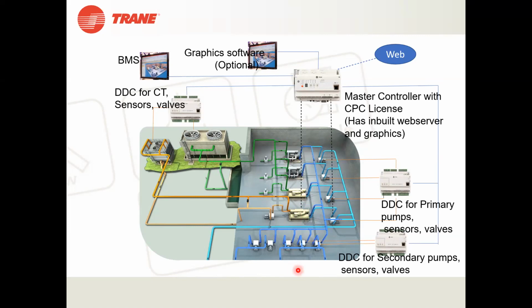But in the afternoon, or any time, if the load is only 20 to 30%, you do not need so many plants, pumps or chillers to run, right? So you will be modulating. The primary will be throwing probably 100% to the secondary, but the secondary is throwing only 50% of the requirement, because the load has been reduced. I will take all the questions after my presentation. Just let me finish this.